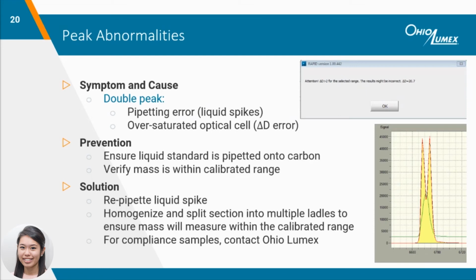Homogenize and split the remaining carbon sections to ensure they're within your calibration range. If a double peak is present but is within your calibrated range, this could indicate a pipetting error or potential interferent. Run a continuing calibration verification and ensure the peak is nice and Gaussian prior to continuing analysis.